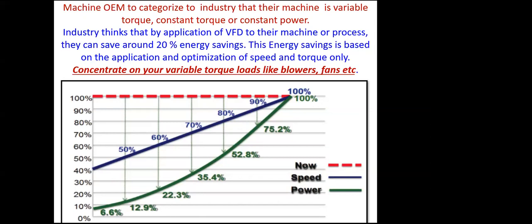What is the maximum flow for the given RPM at the given static pressure, that is the best efficiency point of the blower, is decided by the VFD that is going to be retrofitted on your motor. It gives the optimum torque and the optimum speed for the given blower mechanism to achieve the flow as well as the static pressure and an excellent efficiency of the blower, and the savings is the byproduct as such.